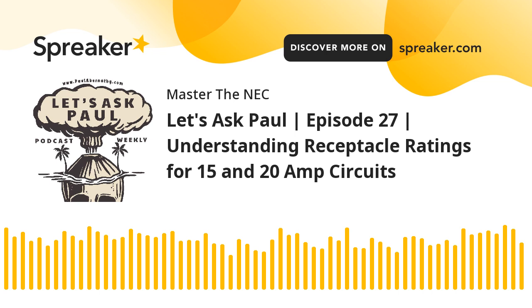Hopefully that answers your question about the ampere ratings. But if you want to see things like 30 amp, 40 and 50 amp ratings and whatnot, then just go look at the allowances in 210.21(B)(3). Go look at what happens if it's a single receptacle in 210.21(B)(1). So yes, I can have a 50 amp rated simplex receptacle on a 40 amp rated circuit as long as my load doesn't exceed the 40 for an individual branch circuit. That 50 amp single does equal or exceed the rating of the branch circuit. So that's why you're able to do that for the single.